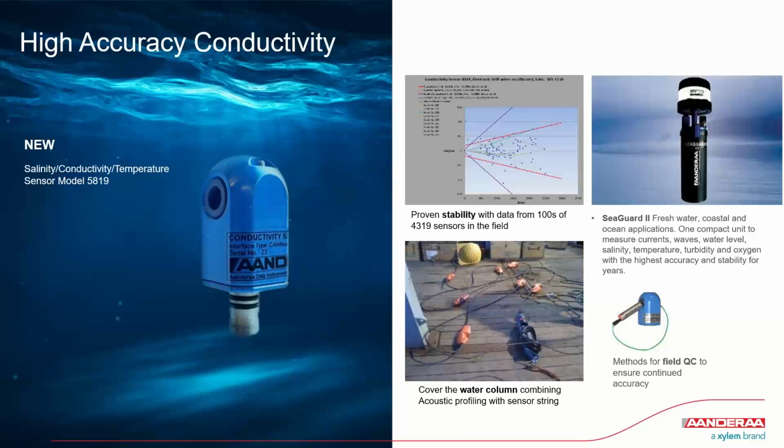For current sensors, we have, for example, a test unit for the single point. We have methods for most of our sensors, for how end users can check them and verify that they are working more or less as they should. It's not calibrations, but it's verifications.